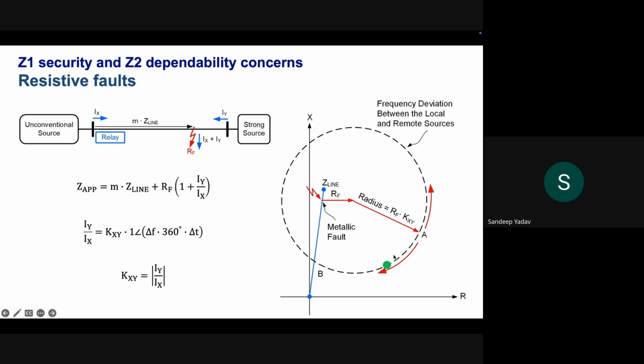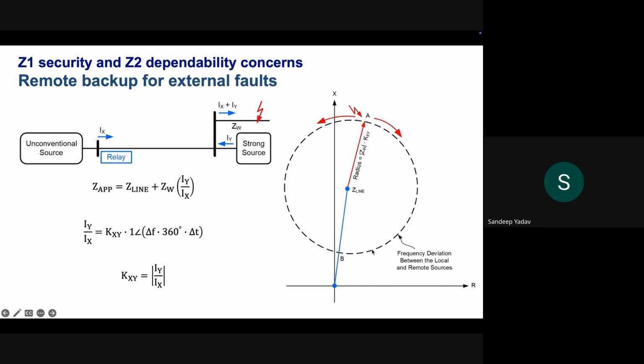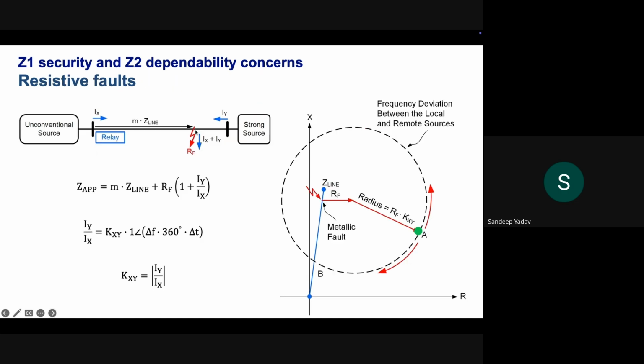So depending upon how the controller will react to this fault, this point could oscillate and it could be anywhere on this periphery, and it depends upon the controller algorithm. The way the controller reacts to the fault, the way the short circuit response of this inverter based resources. Same goes with external. So this was an internal fault in the line.